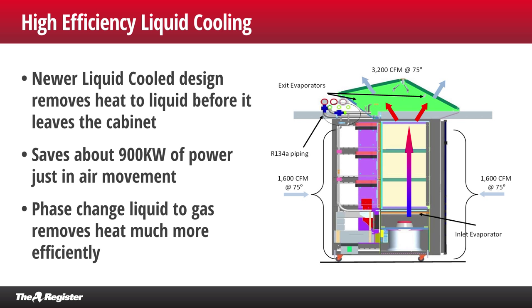It's a very clean, neat technology. Liebert actually developed and sells this as a commercial product — they call it their high-density cooling product — as an add-on for commercial racks in any data center, and Cray adapted it for their machines. The other advantage is that you're not directly attaching anything to the servers themselves — no direct water blocks. In fact, the cabinets can be run air-cooled: Cray can sell the same cabinet in an air-cooled configuration by just pulling off the radiators top and bottom.